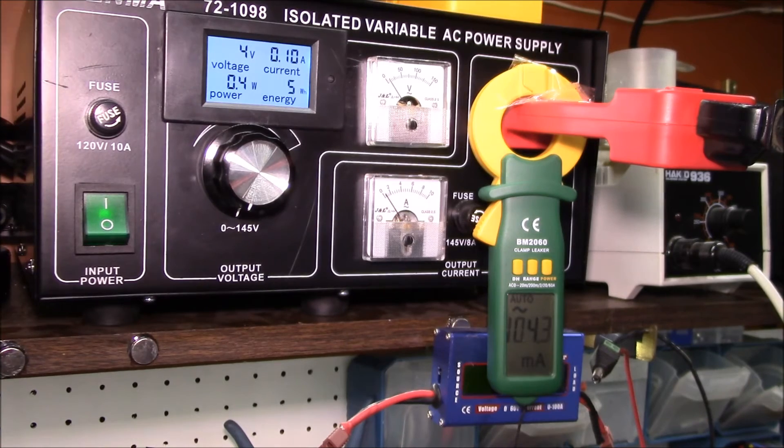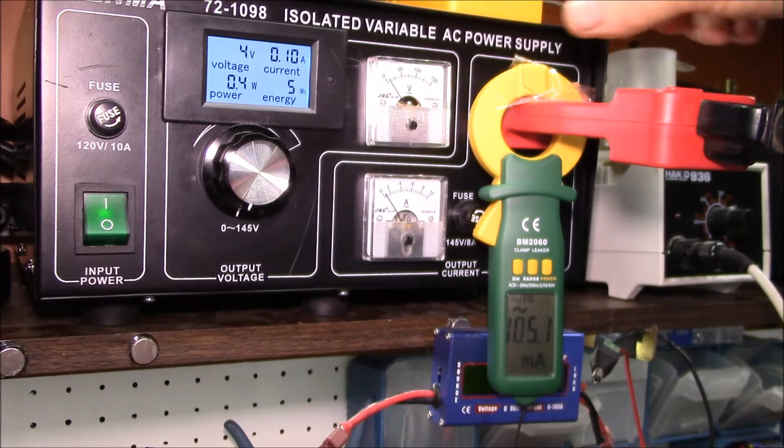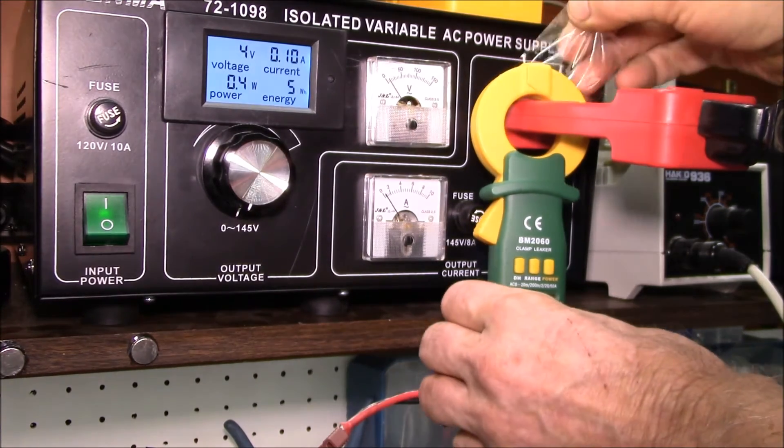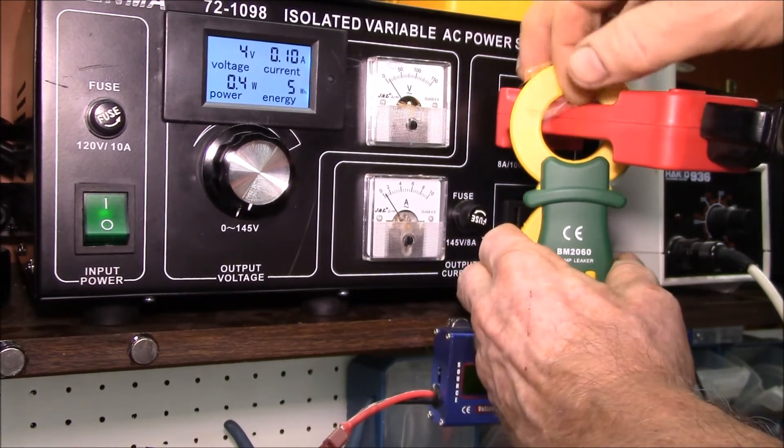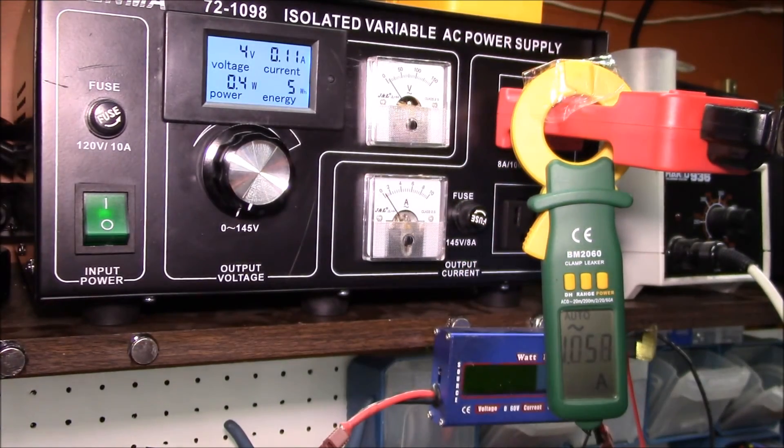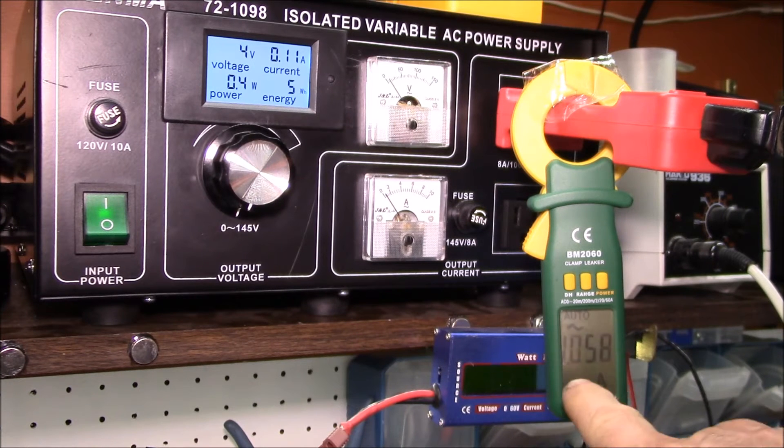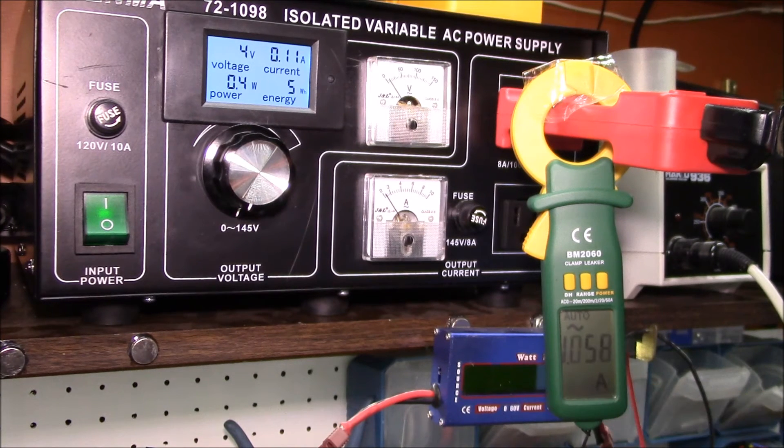Just for grins, we can switch over to the x10 reading. This multiplies the reading by 10, so this one is showing about 106 milliamps. The meter's reading 1.06, but you have to divide that by 10. It looks like it's within half a digit on the low end.